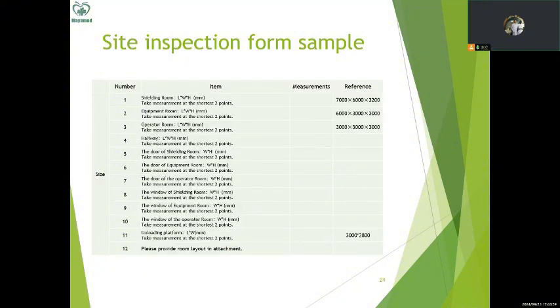And this is another page of the site inspection table. In this table, we pay attention to the size, like we need to measure the shielding room size, length, width, height, and we must take measurement at the shortest 2 points. And also we have the equipment room, we have the operator's room, and we make everything simple. You just visit a site and fill this table, and that's all. And that can help us to make sure the site is okay or not.